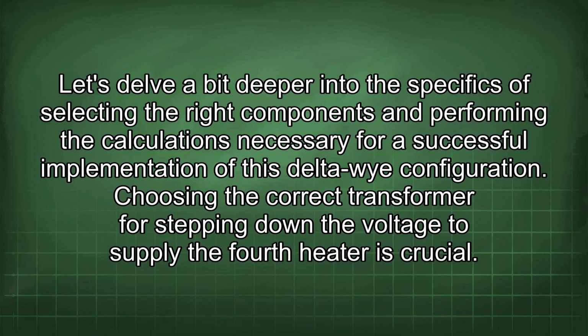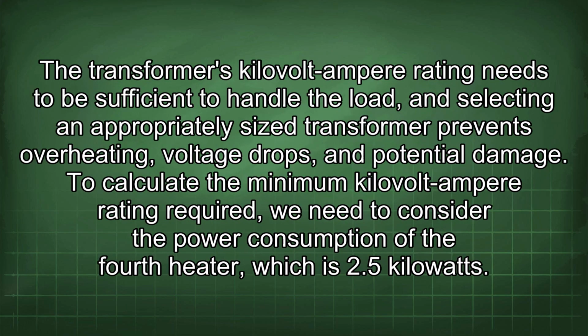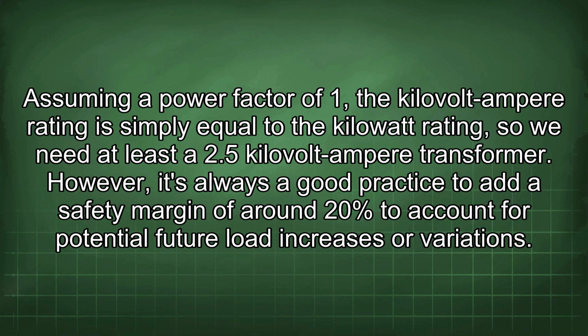Choosing the correct transformer for stepping down the voltage to supply the fourth heater is crucial. The transformer's kilovolt ampere rating needs to be sufficient to handle the load, and selecting an appropriately sized transformer prevents overheating, voltage drops, and potential damage. To calculate the minimum kilovolt ampere rating required, we need to consider the power consumption of the fourth heater, which is 2.5 kilowatts. Assuming a power factor of 1, the kilovolt ampere rating is simply equal to the kilowatt rating, so we need at least a 2.5 kilovolt ampere transformer.